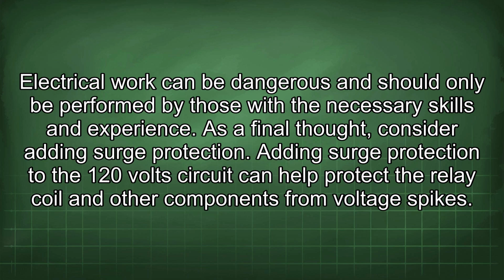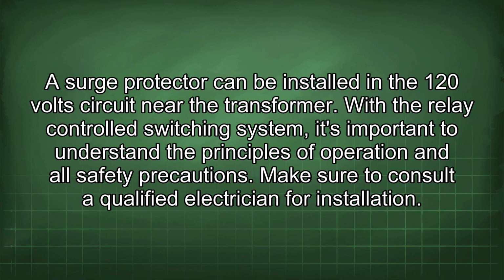As a final thought, consider adding surge protection. Adding surge protection to the 120 volt circuit can help protect the relay coil and other components from voltage spikes. A surge protector can be installed in the 120 volt circuit near the transformer. With the relay-controlled switching system, it's important to understand the principles of operation and all safety precautions. Make sure to consult a qualified electrician for installation.